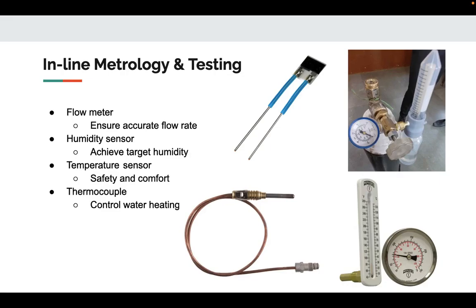So in terms of getting inline feedback within our system, we want to use a flow meter to make sure that the flow rate is actually being accomplished. Going through the bubbler system could affect flow rate, so we want to ensure that it's being maintained throughout the system. We want to have a humidity sensor where we can maybe adjust the water temperature and/or different aspects of the system to accomplish the humidity that we foresee will be useful, which is approximately 50% relative humidity. We want a temperature sensor as a safety measure, making sure that the system does not get too hot and we're not flowing too hot of air into the infant and causing burns. And then we want a thermocouple sensor as well to control the water heating.